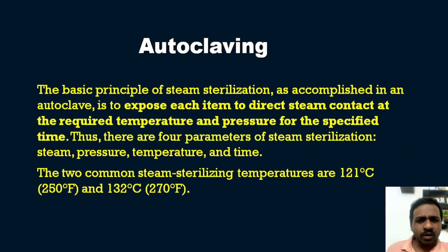And the final option was autoclaving. So what is autoclaving? The basic principle of steam sterilization as accomplished in an autoclave is to expose each item to direct steam contact at the required temperature and pressure for a specific period of time, so that the organisms will die.